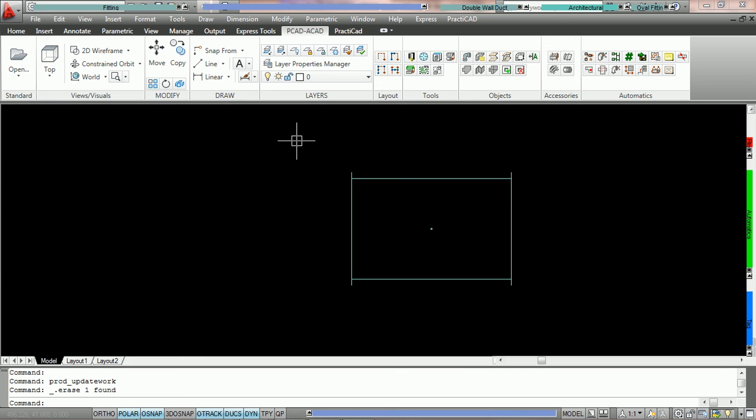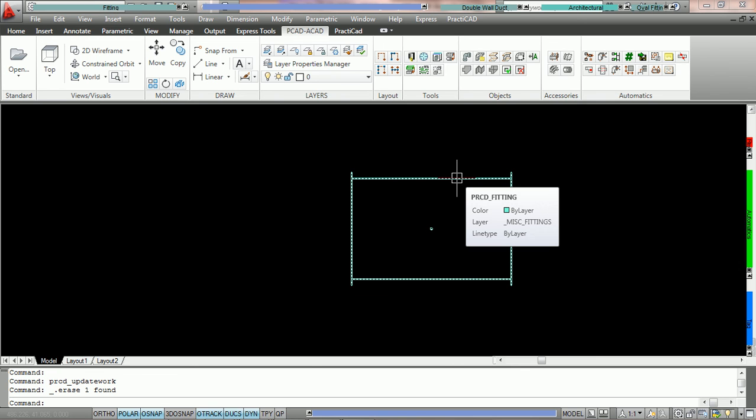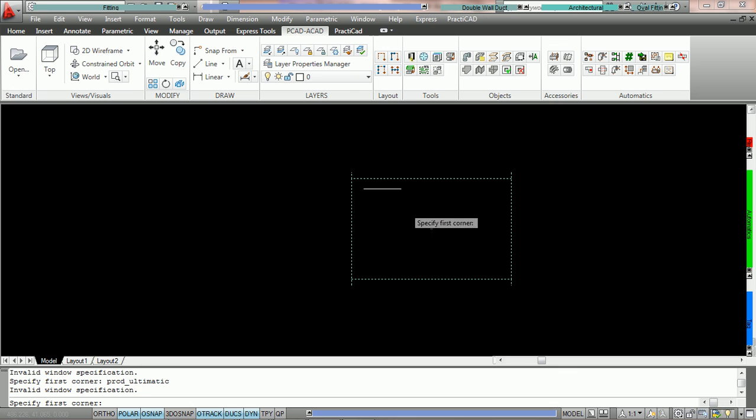And then it's going to kick in the second automatic, which is supposed to change whatever is highlighted green. But because there's nothing highlighted, when that command automatic gets typed into the command line, AutoCAD is going to find the selection set empty, and it's going to stop our Ultimatic right there. It will never be able to go to the third line of the Ultimatic that says highlight all the fittings on the drawing with zone equals return and then change it red. And you're going to notice that right now we're going to fire off this Ultimatic by clicking zone color change once. And you can see that we're stuck. It never completed the Ultimatic.